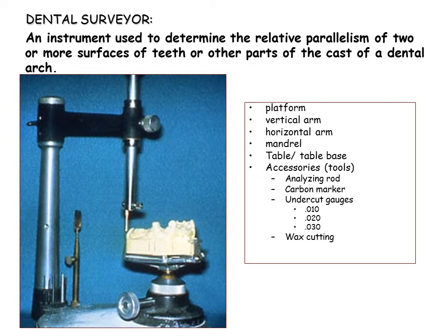6. The mandrel is a vertical rod for holding special tools. 7. Analyzing rod and accessory tools. These tools contact the convex surface to be studied in a tangential manner. The relative parallelism of one surface to another may thus be determined. 8. By substituting a carbon marker, the height of contour may be delineated on the surfaces of the abutment teeth and also areas of interference requiring reduction or block out.